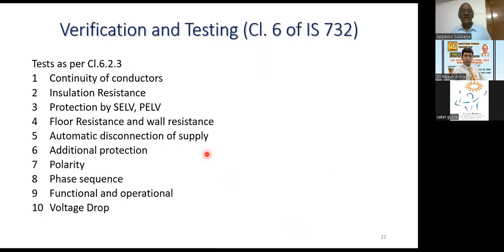And this is the verification testing. This is nothing but as per clause 6 of IS 732 and as per clause 6.2.3, these are the tests available. For example, continuity of conductors, meaning first the protective conductor, the working conductor, to make the automatic clearance of fault, to ensure that, the loop impedance. So there are a lot of tests.